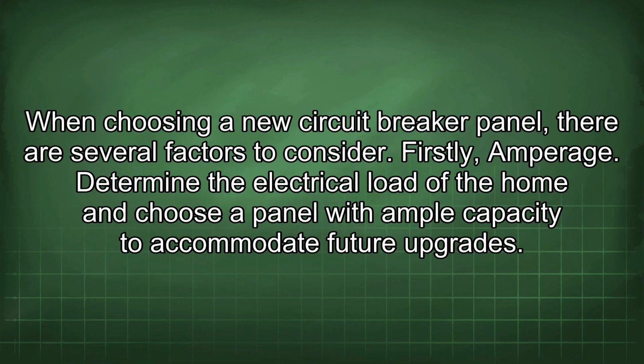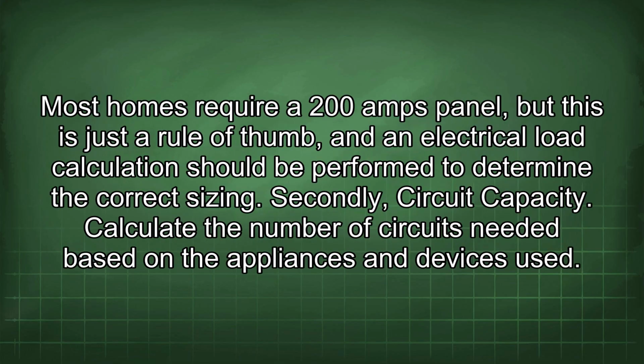When choosing a new circuit breaker panel, there are several factors to consider. Firstly, amperage: determine the electrical load of the home and choose a panel with ample capacity to accommodate future upgrades. Most homes require a 200 amp panel, but this is just a rule of thumb, and an electrical load calculation should be performed to determine the correct sizing.